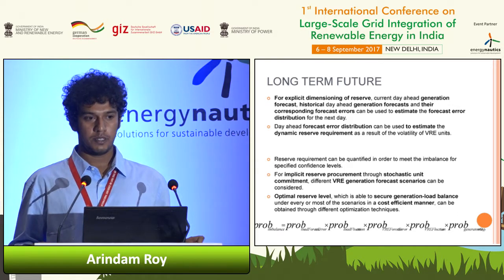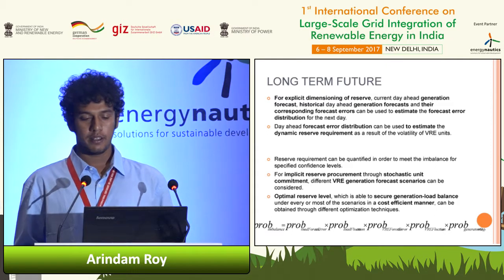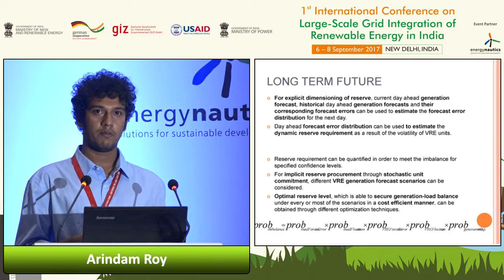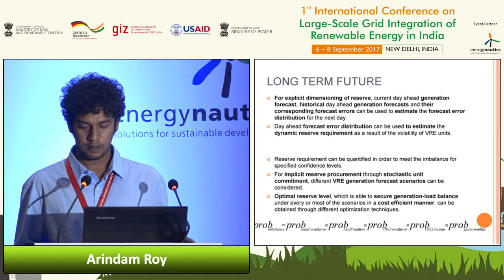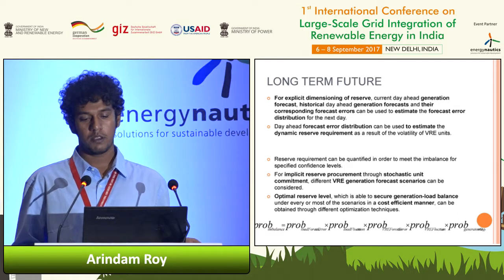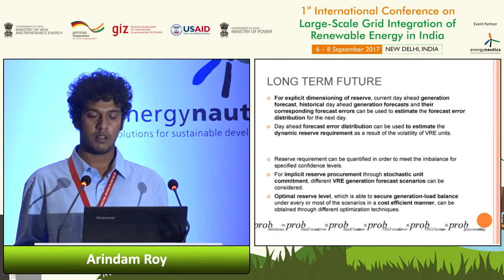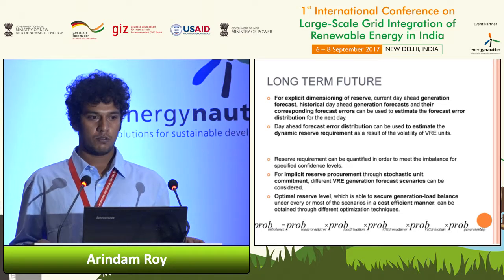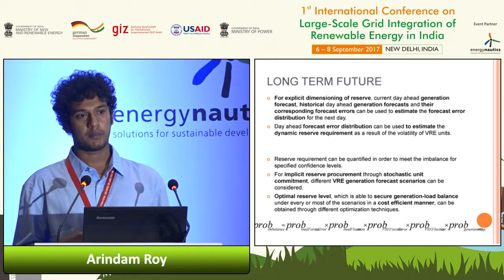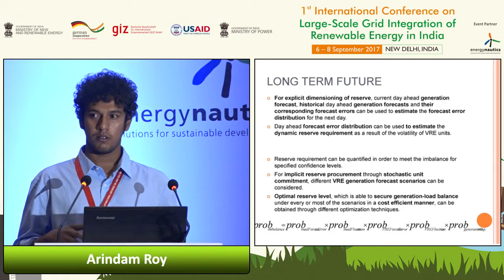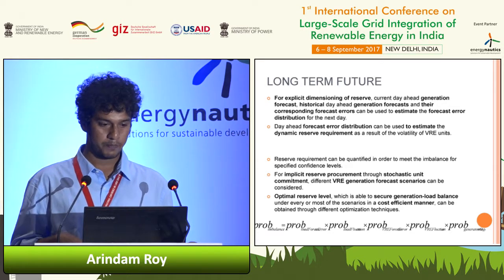The DLR, which is used for real-time line rating, can also be used in a day-ahead framework. There are already papers in literature which show that it may be possible to use the DLR in a day-ahead framework in a probabilistic manner, so as to know the expected capacity on a day-ahead basis and the range of errors associated with that.